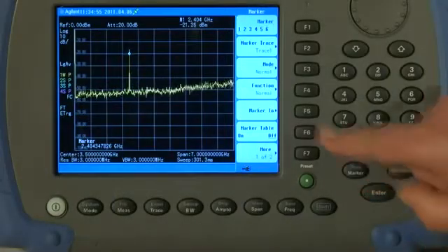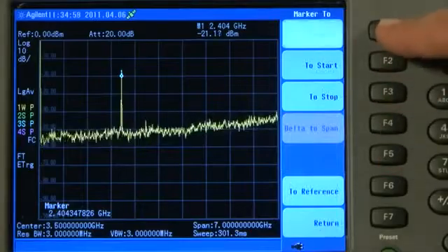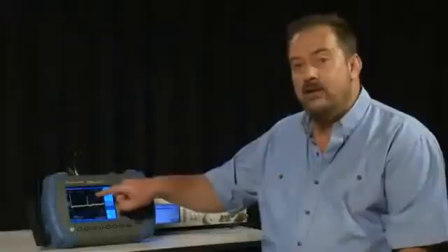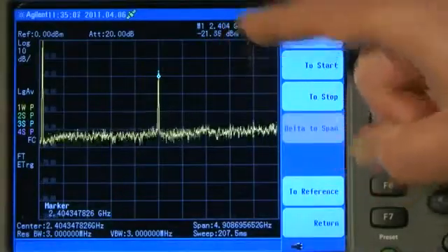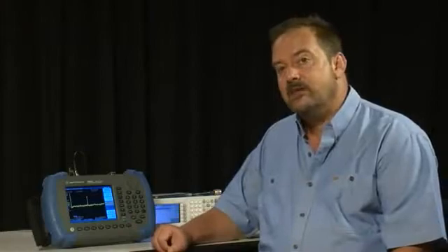And I can then press the Marker button and press Marker To, Center Frequency. So that has now tuned that 2.4GHz signal to the center of the screen. You can see here it says 2.404GHz. So it is roughly in the center of the screen and I did not need to know what the frequency of it was.